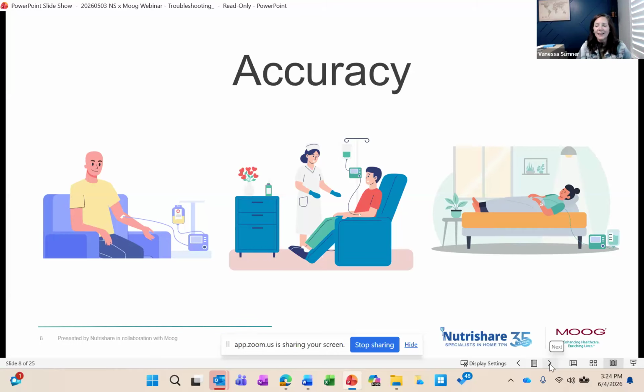This head height effect happens because the tubing in the pump can stretch slightly. When the fluid bag is positioned higher than the pump, that section of tubing is under a bit more pressure from gravity, which causes it to expand and fill more, pumping more fluid. When the bag is at the same height as the pump or lower, the pump essentially has to pull the fluid, similar to siphoning, and that segment might not fill as much.